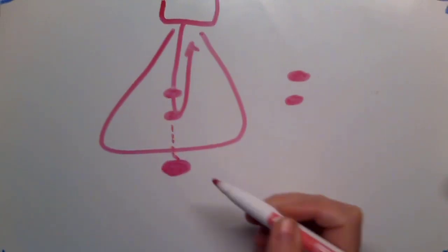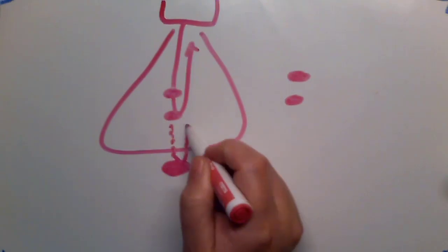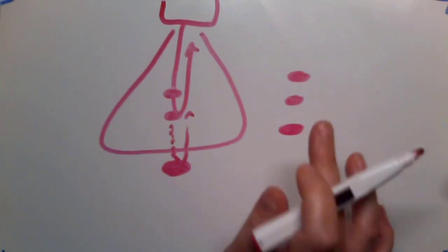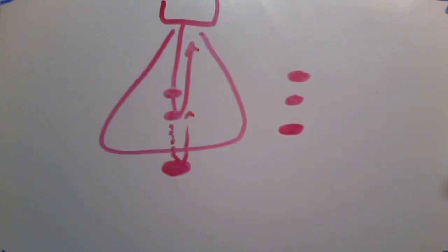But what if we had a really, really strong reflector down here? So that sound kept traveling, and now those echoes are coming back while the next picture is being created. That really strong reflector is going to show up in our picture. And it's going to show up in a random spot because the machine thinks that it came back from the current picture that's being made. So range ambiguity artifact is kind of similar to aliasing in that this deep reflector is being displayed in the wrong spot, and it's because the machine didn't realize that that was from a previous echo or previous pulse that had already been sent out. So we're getting a latent echo from a previous pulse being displayed in our picture.